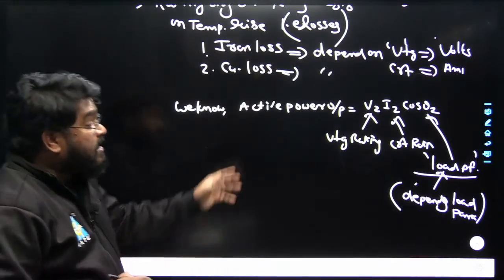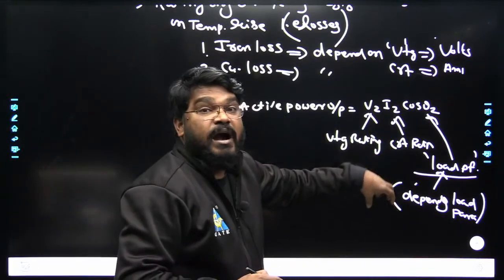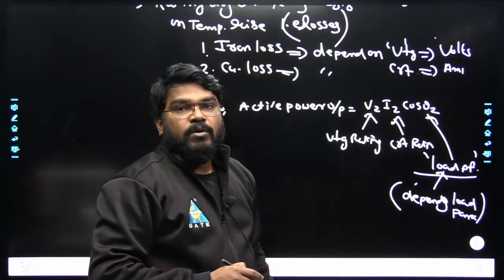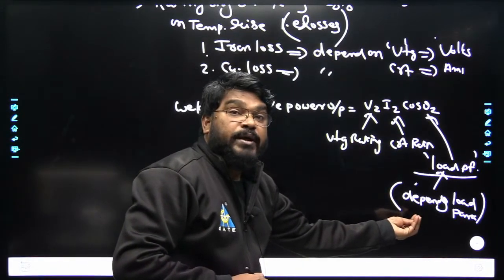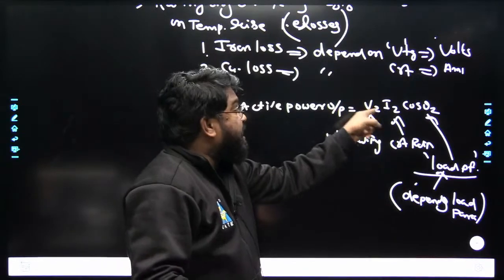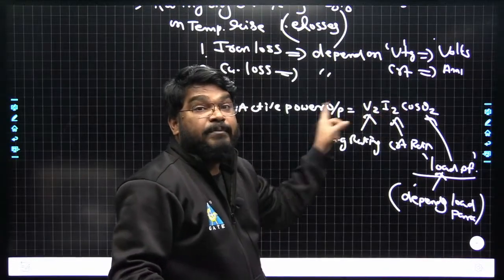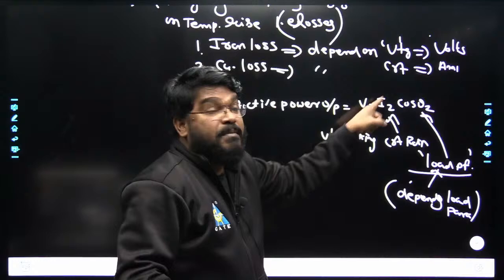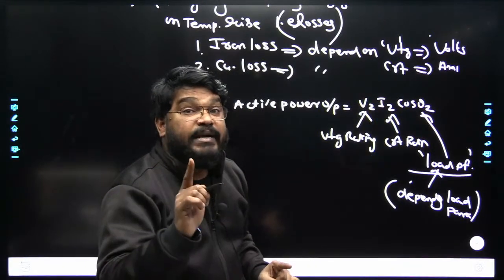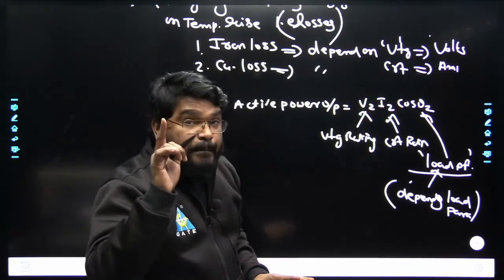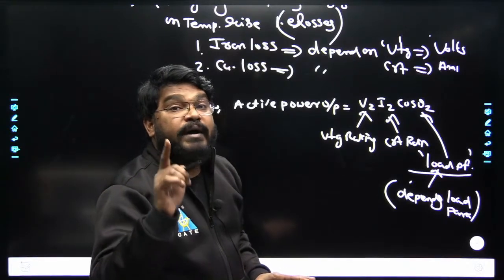Since the manufacturer doesn't know the load power factor during design, they consider the highest possible power factor of the load, which is 1. If power factor equals 1, then the active power becomes equal to the apparent power, which is why rating is measured in apparent power instead of active power.